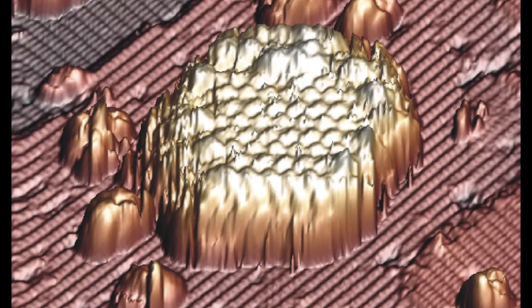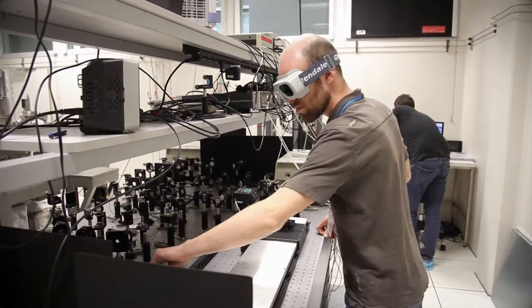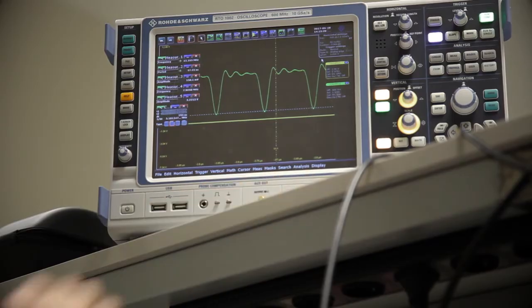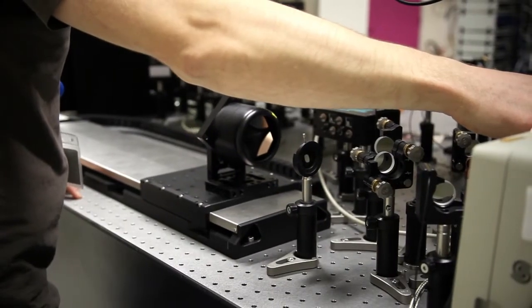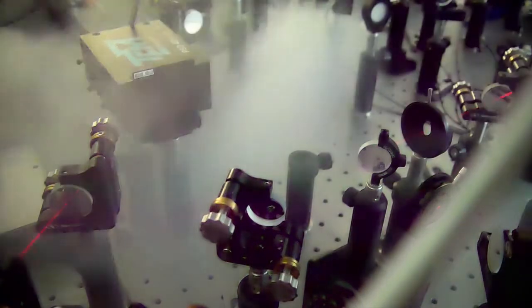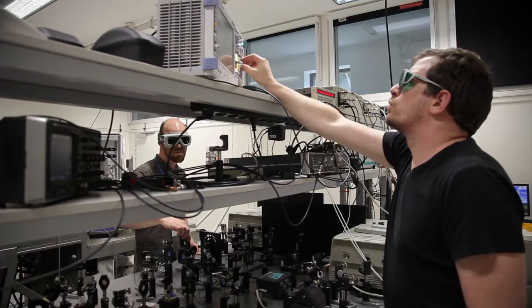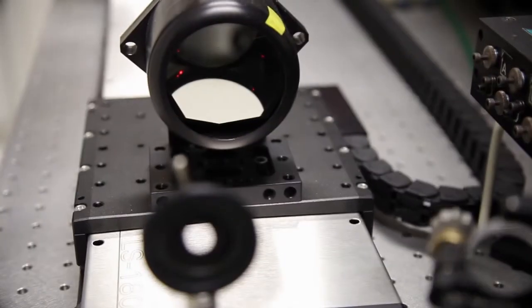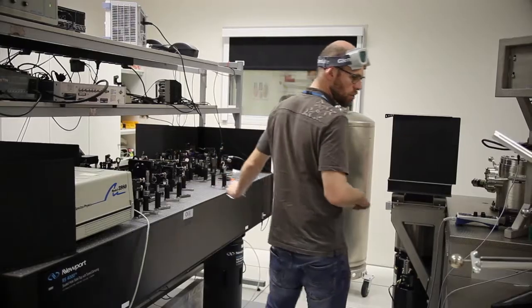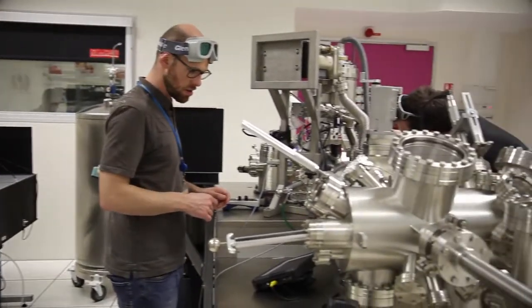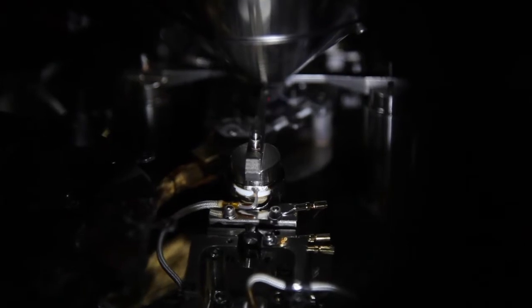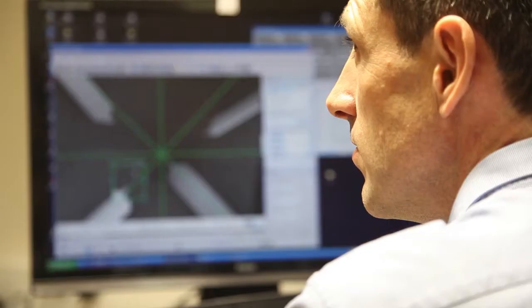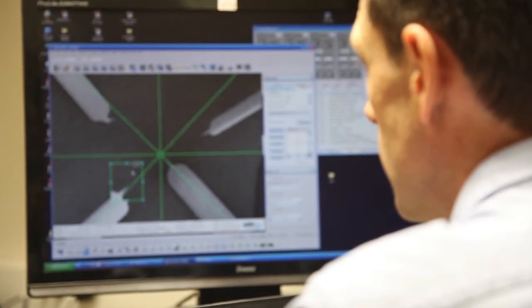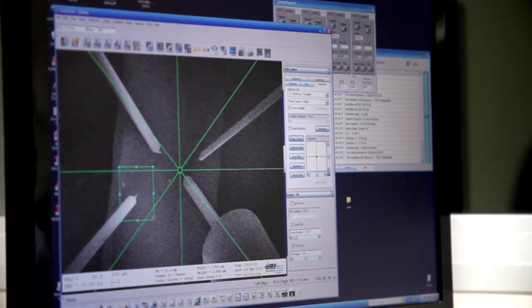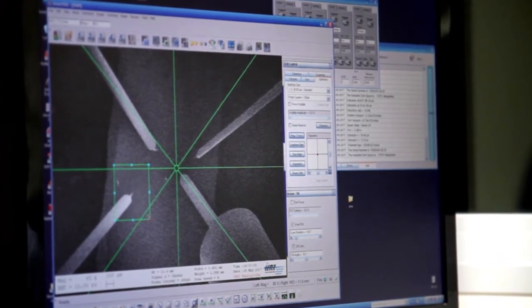One major goal of the Excelsior project was to combine these scanning probe microscopes with a femtosecond resolution pulsed laser excitation system to probe electron dynamics with sub-nanometer spatial resolution. The technique relies on the measurement of a transient photocurrent with STM upon optical excitation of a sample with ultra-fast laser pulses. The successful control over the pulse delay modulation using pulse-picking techniques opens the way to visualize the transient carrier dynamics in nanometer scale structures with a temporal resolution below the picosecond.